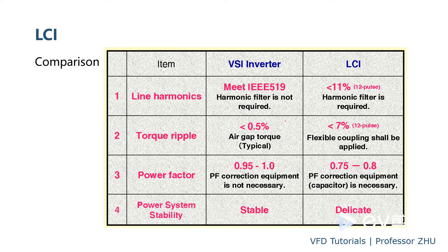The fifth and the seventh odd harmonic, majority of those harmonics will be canceled. So the only left harmonic will be, as we discussed before, will be K times P plus minus one. And here P is 12 because of 12-pulse. So the majority of harmonics is 11th, 13th, 23rd, and 25th. In a lot of cases, 12-pulse still cannot meet the IEEE standard or other standard. So you will have to set an extra power filter and also power factor correction because of the power factor is very low on the low, low condition.